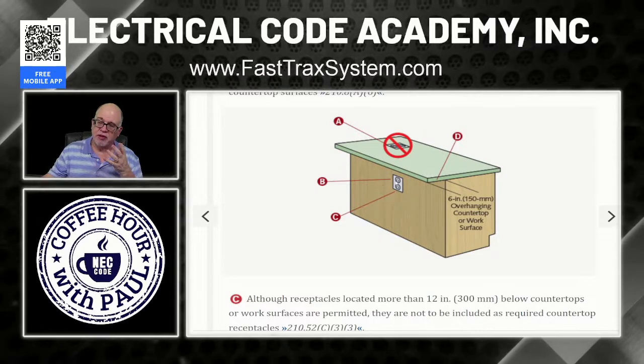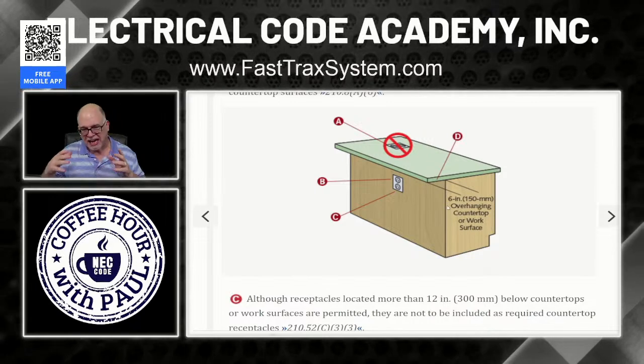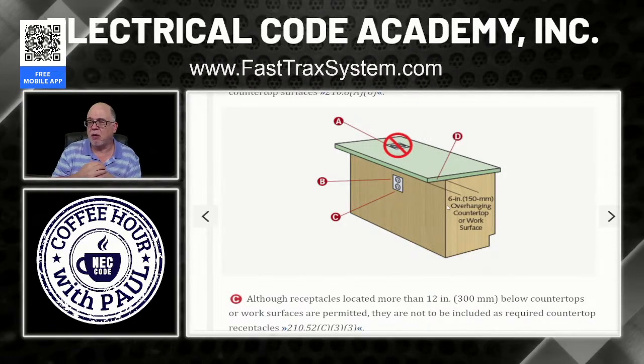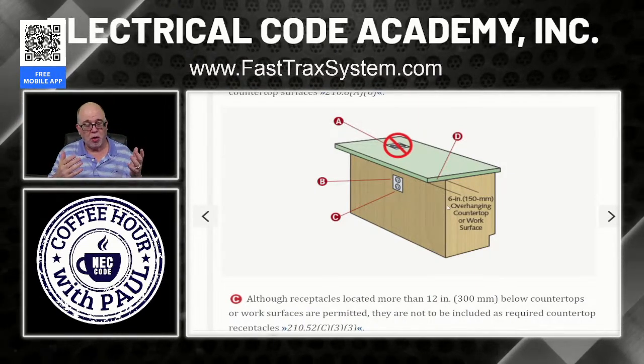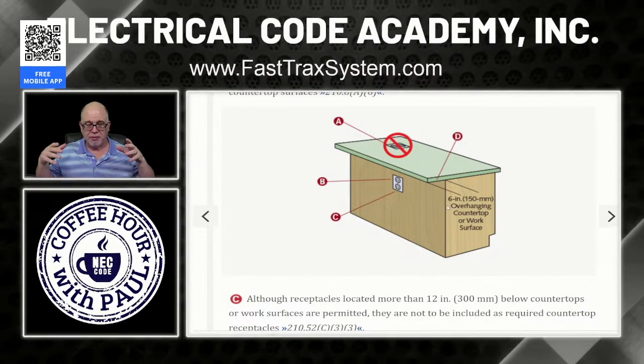But remember, this receptacle to serve the countertop cannot serve the wall space. Okay, so the construction of the island can make a big difference. If it's just cabinets there with the top on it, it is not a wall, and I would not consider it wall space. But if it's a framed up wall and you're pushing cabinets to it and putting a counter on it with an overhang, and if you go into construction and you notice they frame it up, my house was like that. It was framed up.